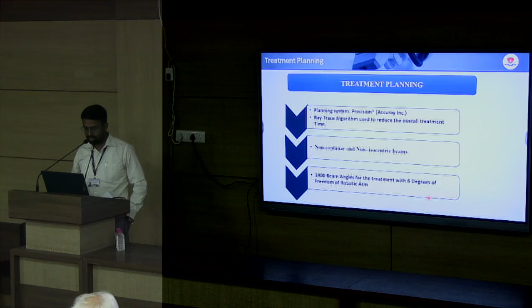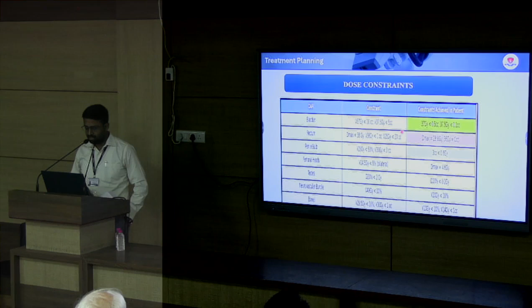So here comes the treatment planning. In planning, we have a ray trace algorithm used to reduce the overall treatment time of the patient. We have many non-coplanar and non-isocentric beams that are applicable only in the CyberKnife system, and we have 1400 beam angles for the treatment with 6 degrees of freedom of the robotic arm. After the treatment planning, the dose constraints have been achieved, and the general dose constraints that are followed, and we have achieved for bladder, rectum and penile bulb, which are considered priority OARs, are well within the guideline limits.